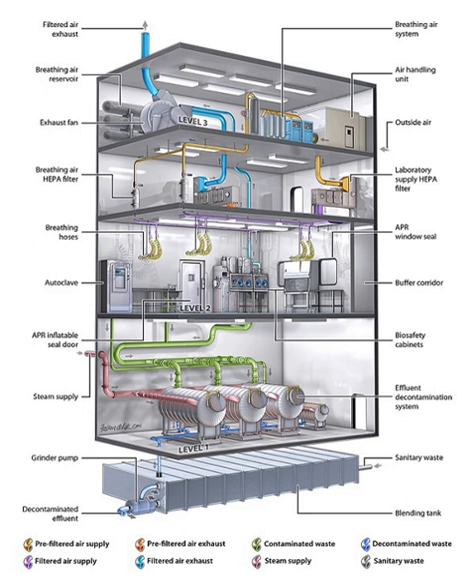In addition, the facility which houses the BSL-3 laboratory must have certain features to ensure appropriate containment. The entrance to the laboratory must be separated from areas of the building with unrestricted traffic flow. The laboratory must be behind two sets of self-closing doors to reduce the risk of aerosols escaping. The construction of the laboratory is such that it can be easily cleaned. Carpets are not permitted, and any seams in the floors, walls, and ceilings are sealed to allow for easy cleaning and decontamination. Windows must be sealed, and a ventilation system installed which forces air to flow from the clean areas of the lab to the areas where infectious agents are handled. Air from the laboratory must be filtered before it can be recirculated.